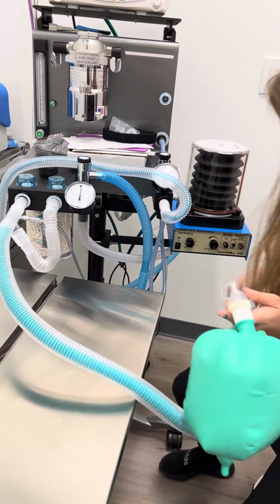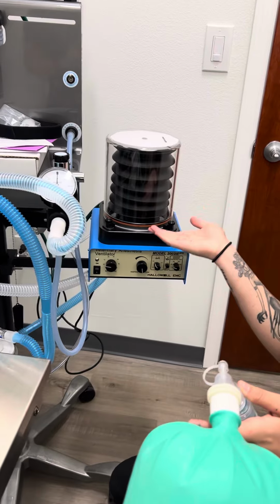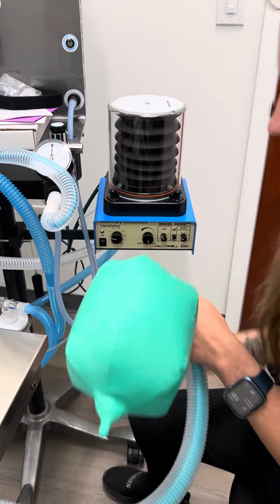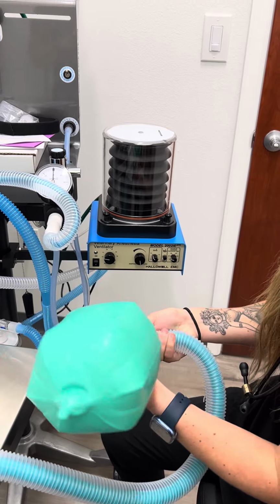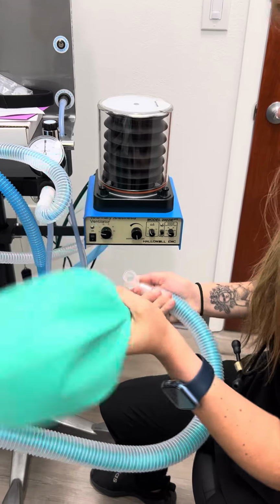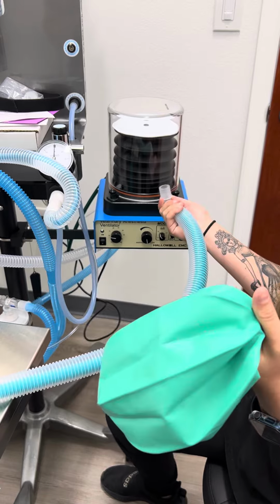All right. So now the bellows isn't falling, there's not a leak in it. Take that out. Okay. If there were a leak, the bellows would start falling like that.